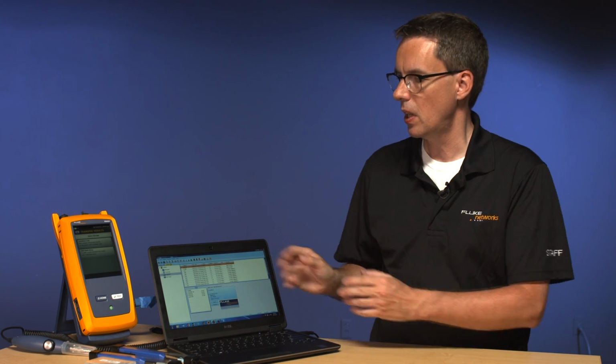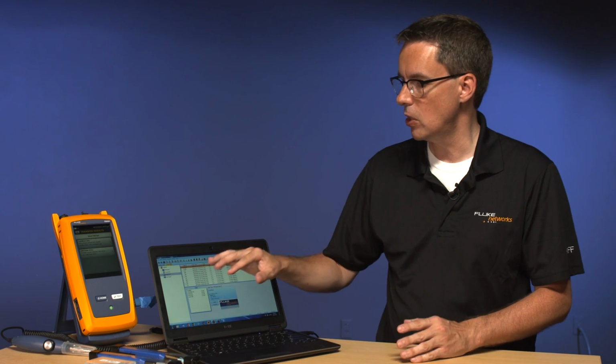So with our results in Linkware, what we prefer to do is to give the customer the results in its native format, that is in the Linkware format. So save it, and you'll save it as a .flw file. You do have the option up here of creating a PDF, and you don't need PDF software. The PDF creator is built into here, so you can hand those results off as a PDF. I highly recommend not doing that. The reason why is the PDF is a summary of the information. It's much better to have the original data on there.